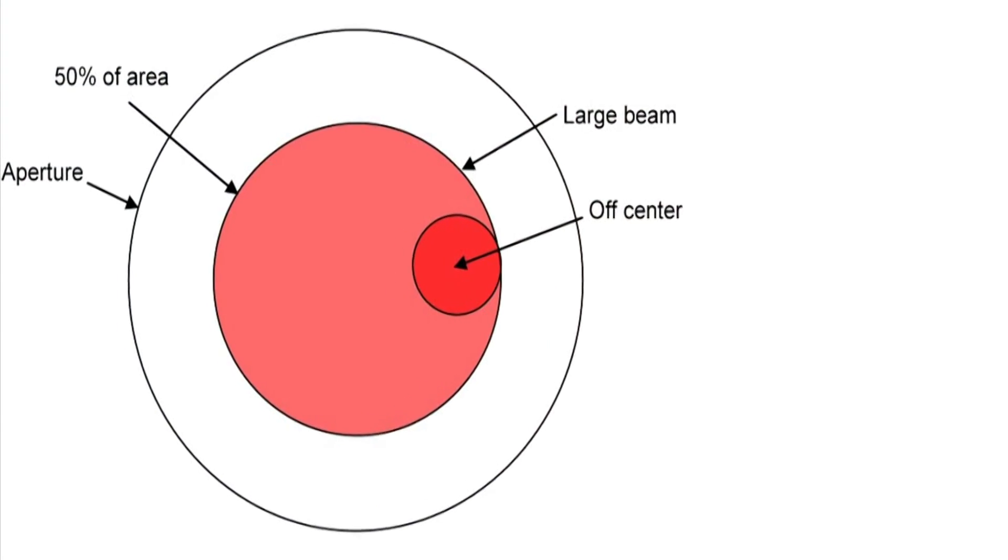One of the other possible errors is uniformity over the sensor. When we calibrate the sensor, we center the beam and we have a beam size that is not large. It's usually no more than one-third of the aperture. Now what happens if the user wants to measure with a very large beam or a beam that's off towards the side? That gives you an extra error.